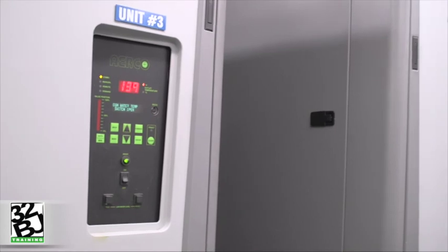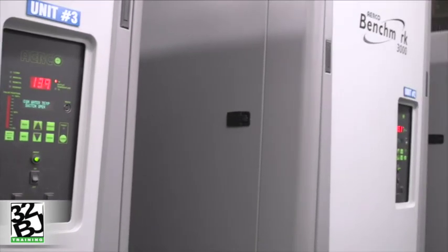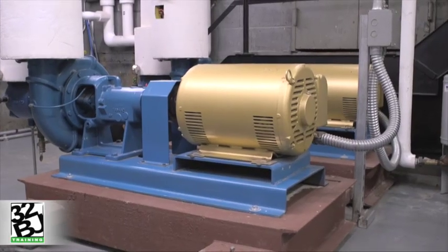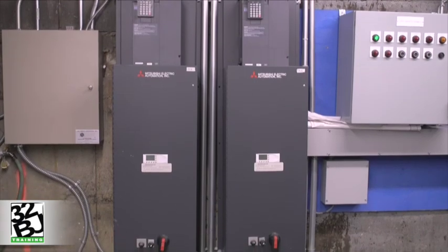Although any type of boiler can be used to provide the mechanical hot water or steam required for the indirect hot water system, the efficiency of this system relies heavily on the efficient combustion taking place at the boiler. This building highlights efficiency by using a hydronic condensing hot water boiler in order to produce that mechanical water. In conjunction with that, they're using high-efficiency pumps controlled by variable frequency drives, which also significantly increase the efficiency of the overall system.